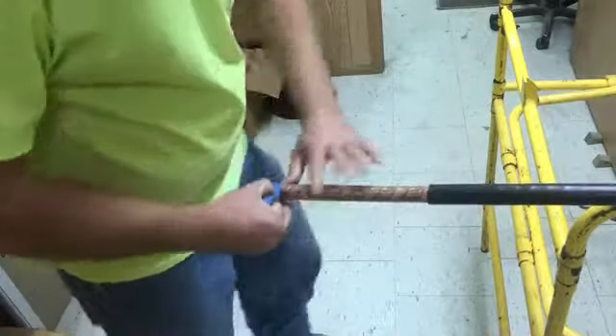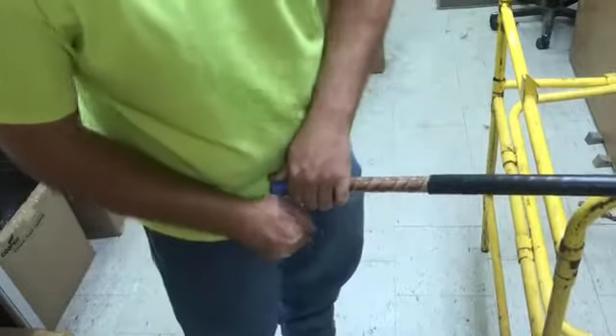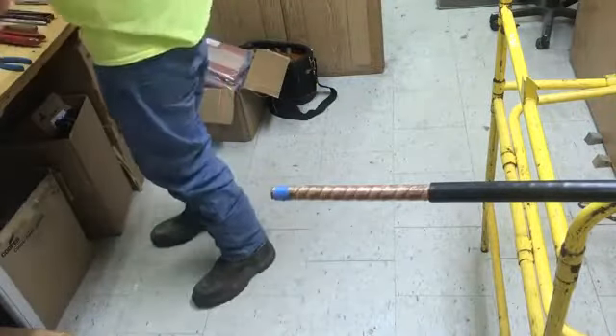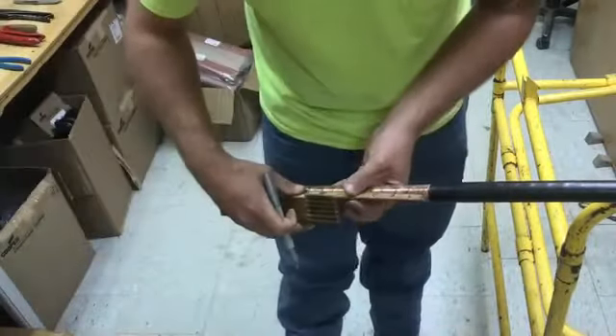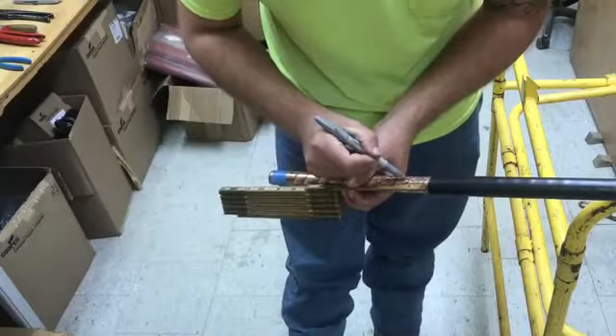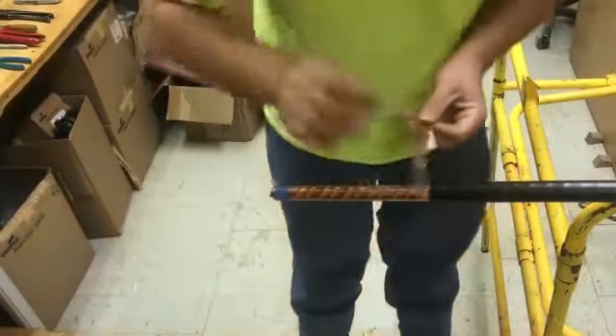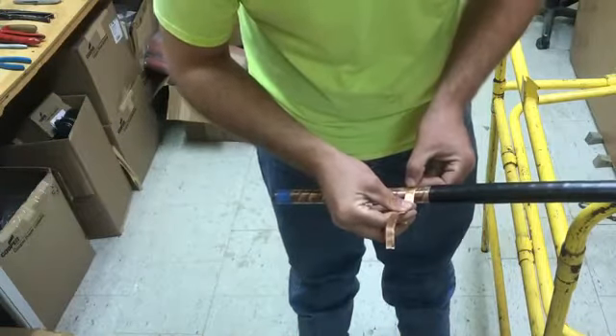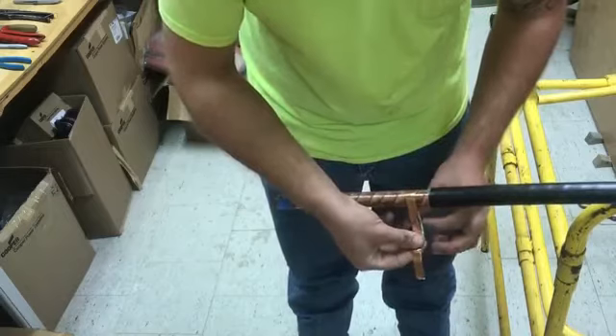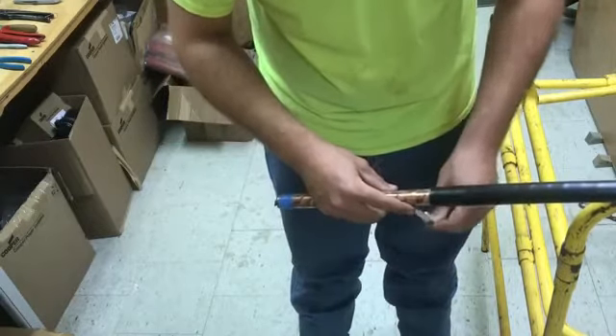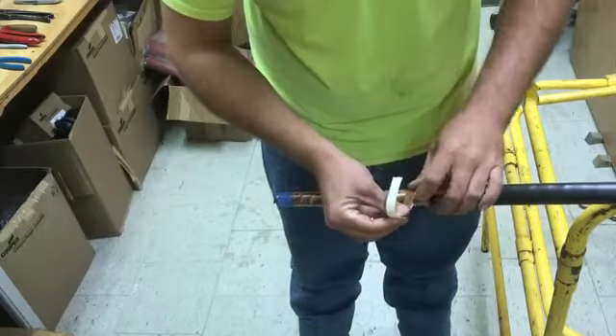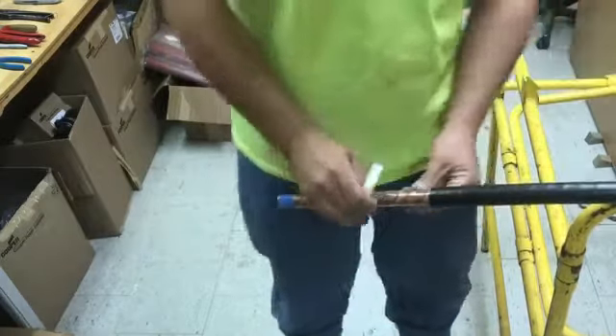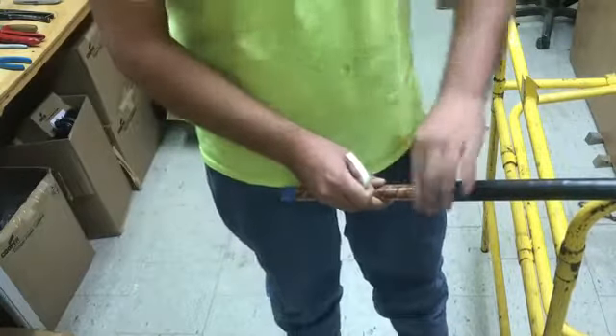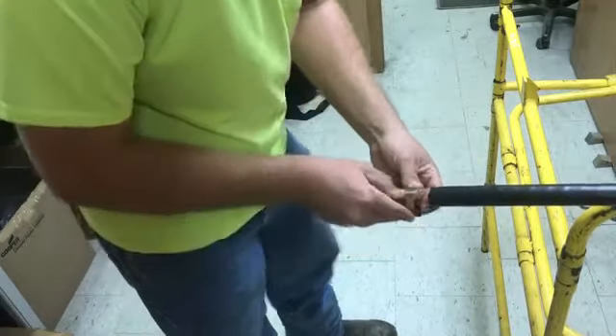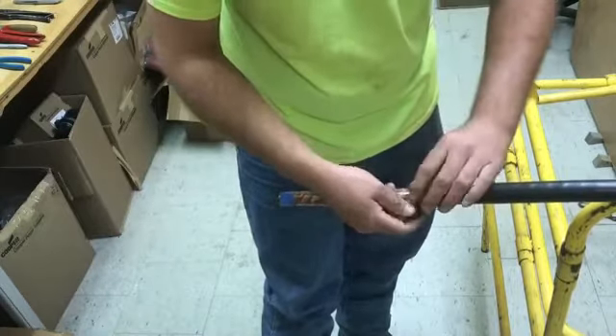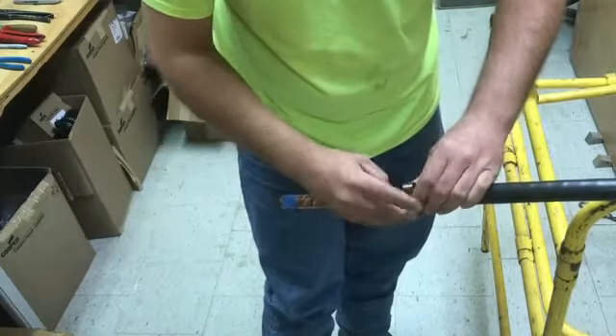I apply a piece of vinyl tape to the end of the tape shield as not to allow the copper tape shield to unravel. I will then measure out the copper tape shield cutback length and then apply a piece of copper tape with the leading edge on the mark I've made. I will then apply a constant force spring to the leading edge of the copper tape. This will allow me to pull back the copper tape and tear against the constant force spring.